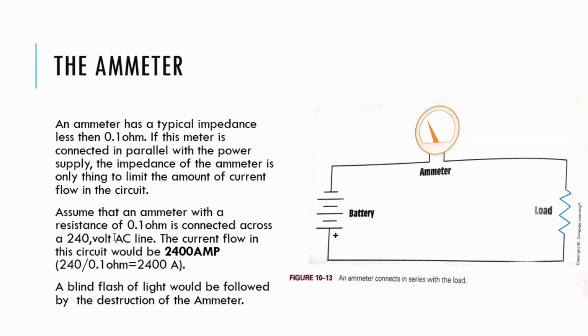Assume that an ammeter with a resistance of 0.1 ohm is connected across, meaning parallel, not in series, to a 240 volt AC line. The current flow in this circuit would be 2400 amps. With this calculation, a blinding flash of light would be followed by the destruction of the ammeter. Only use the ammeter in series, not in parallel.